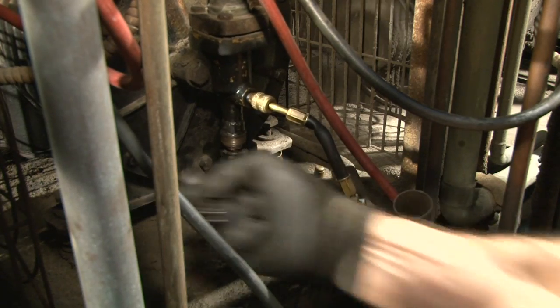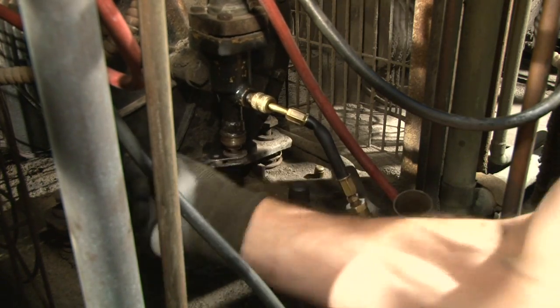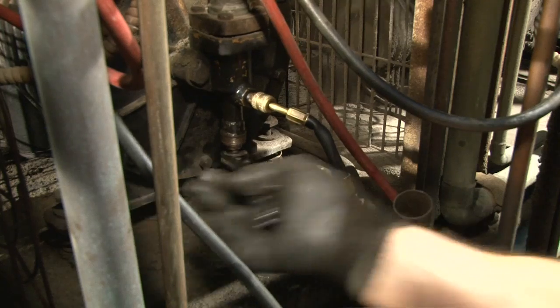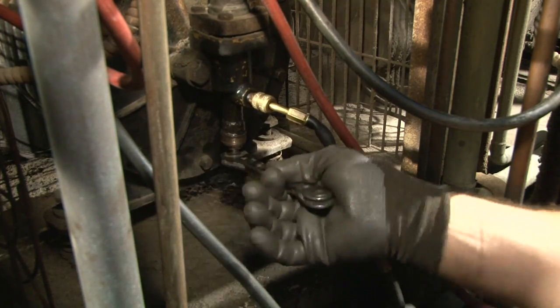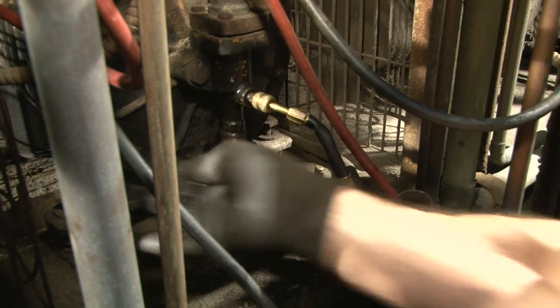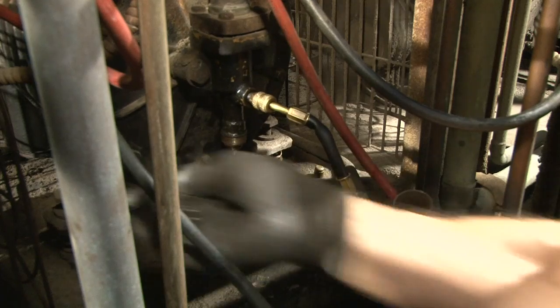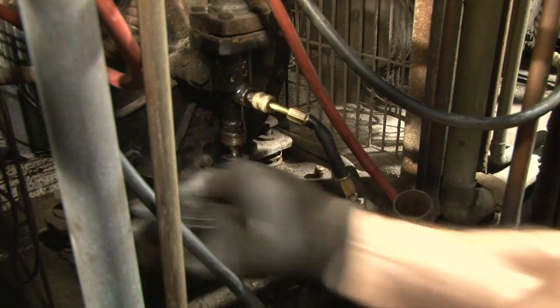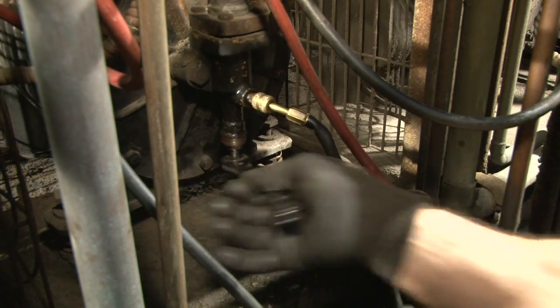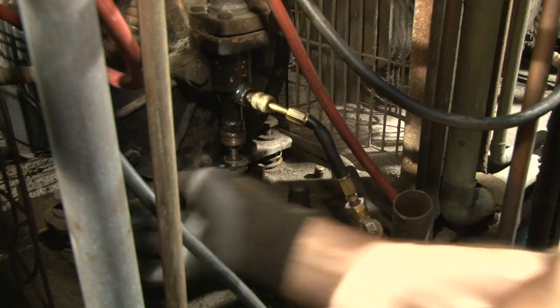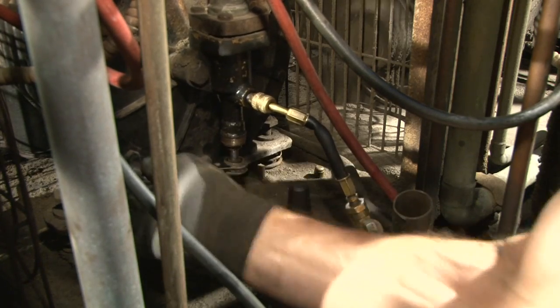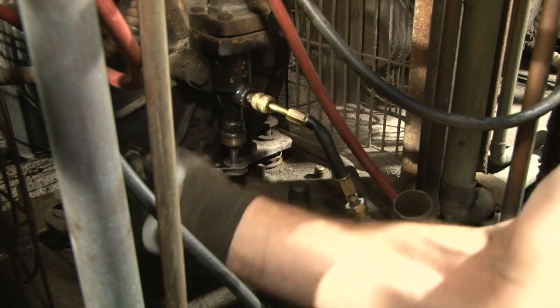The technician now moves to the back side of the compressor on the suction port, and using the access service wrench once again opens the access valve stem on the suction side valve. He does this by moving the stem in a counterclockwise direction until it is fully retracted.